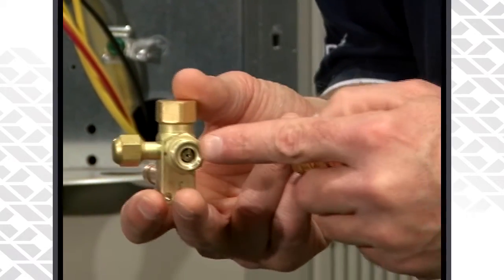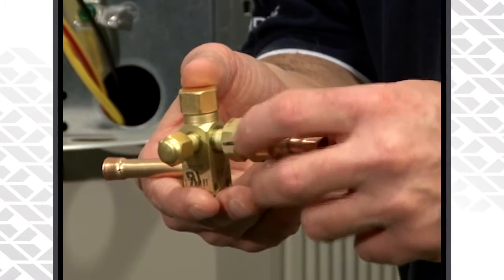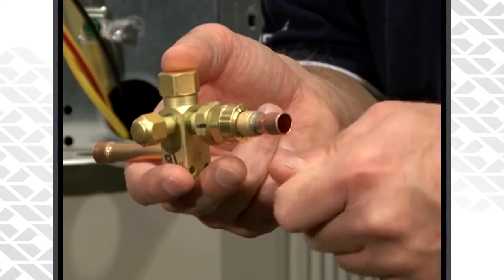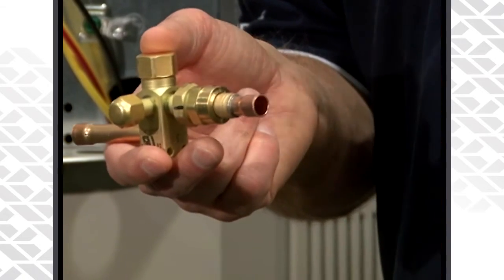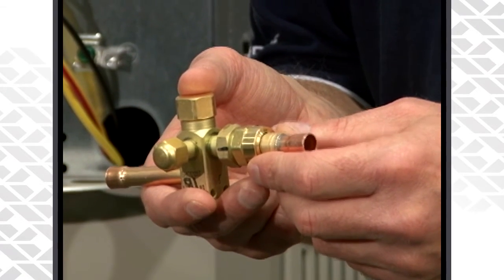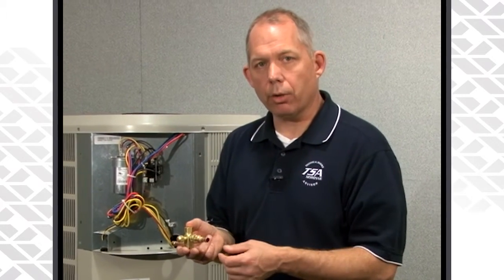Once you've installed the piston, go ahead and screw on the liquid line itself and then cinch it down another quarter turn. It's a metal-to-metal seal, so you should be good to go and leak free. Prior to changing out the piston, I'd recommend brazing your liquid line on first, then making your piston change, screwing everything together, and then you're good to go on the liquid side.